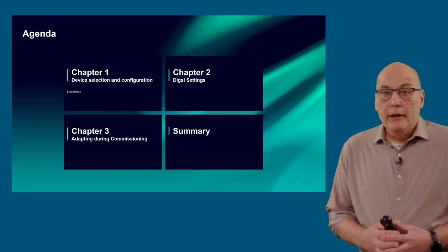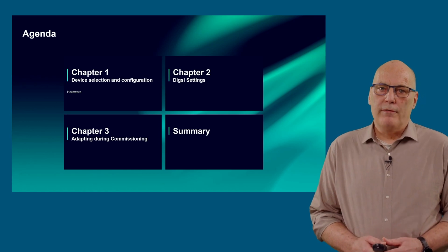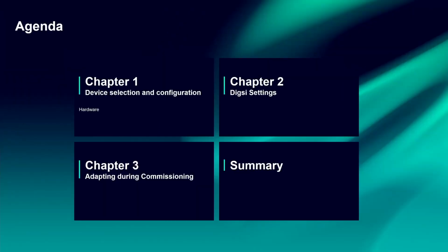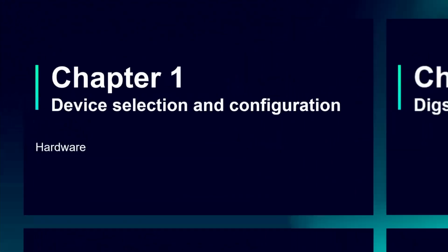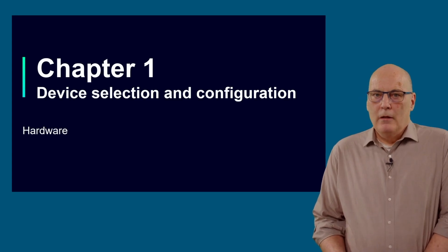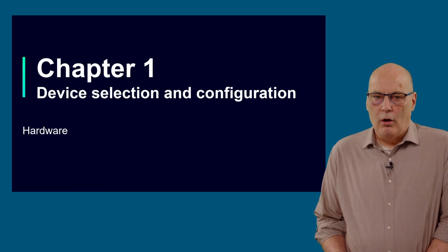The presentation will be in 3 chapters and we will conclude with a brief summary. Chapter 1 provides some general information on the equipment required. The SIPROTEC 5 device selection is also covered. Chapter 2 shows how the configuration with DIGSI is done, highlighting the method of operation and the calculation of setting parameters. Chapter 3 summarizes the methods applied during commissioning to check the correct operation and the adaptation, fine-tuning of the settings. So, let's then start with Chapter 1. The device selection and configuration as well as hardware requirements.